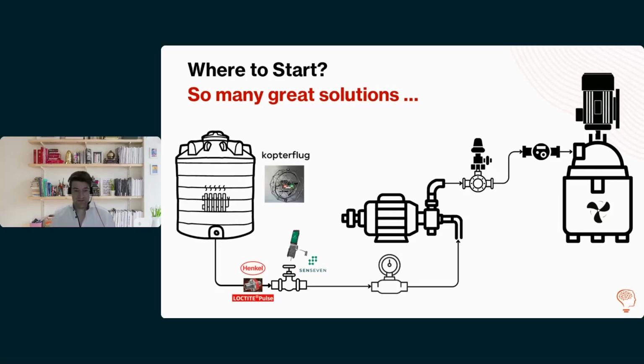I will have valves, or various kinds of valves, in this installation. A lot of the valves that are supposed to close, for example the outlet of a tank, we know a larger percentage of these valves is not completely tight. There is an internal leakage. Senseven from Austria, for example, has developed a technology that allows you to listen to your valve and monitor and quantify the leaks.